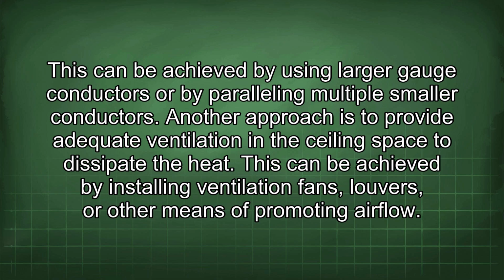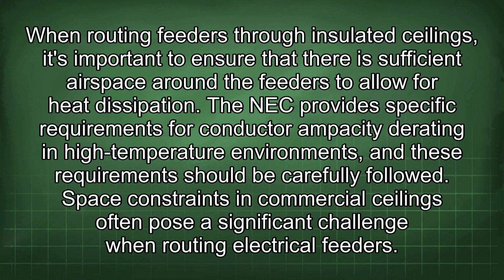Another approach is to provide adequate ventilation in the ceiling space to dissipate the heat. This can be achieved by installing ventilation fans, louvers, or other means of promoting airflow. When routing feeders through insulated ceilings, it's important to ensure that there is sufficient airspace around the feeders to allow for heat dissipation. The NEC provides specific requirements for conductor ampacity derating in high-temperature environments, and these requirements should be carefully followed. Space constraints in commercial ceilings often pose a significant challenge when routing electrical feeders.